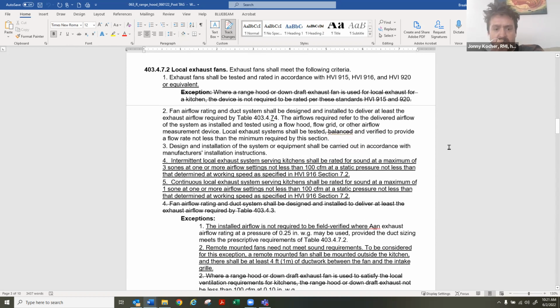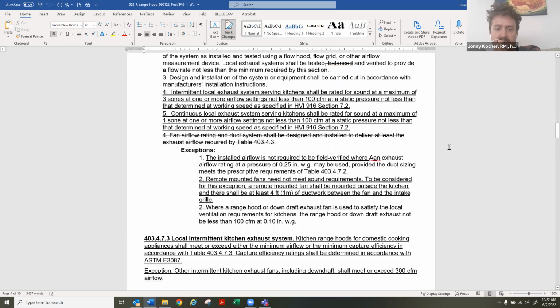Yeah, here we are basically just adding the sound requirements to 403.7.2 instead of in a separate section, because this is already putting in requirements for local exhaust fans. This is for intermittent local exhaust systems serving kitchens, which is basically range hoods or downdraft hoods. We broadened the language so it isn't just specific to range hoods, since there are other kinds of local exhaust. That answered one of the concerns, I believe, that Valerie had. And then we added in some specific language around where the ductwork should be.